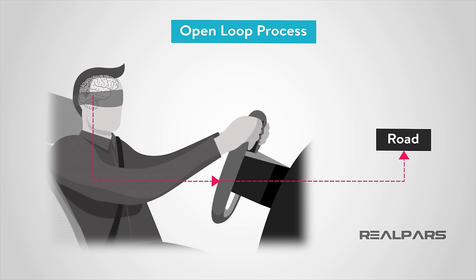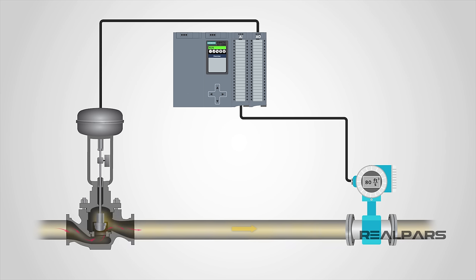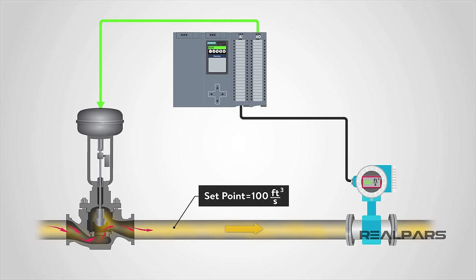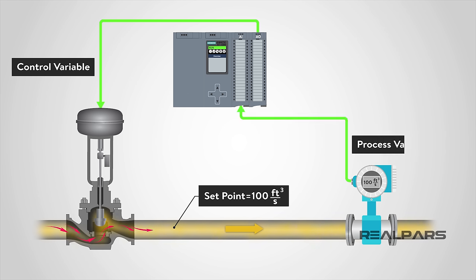Obviously, a much more difficult process to control, and on occasion, you may run into this type of control in your career. In an industrial plant, since there are many factors that we need to consider, we need a robust controller that takes our parameters into account and does hundreds of calculations to determine where the process is and where it needs to go. Say we need to control gas flow through a pipe. The setpoint of gas flow is calculated based on a calculation of some factors, and this setpoint can change at any time. We will control this flow based on a modulating valve — the more open the valve, the more gas allowed to flow. The requested position of the valve is our control variable. Downstream of this modulating valve, we have a flow meter that will measure the gas flowing through the pipe. This is our feedback, or our process variable.